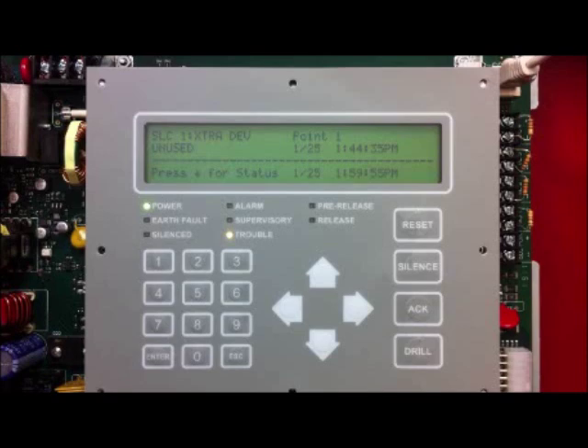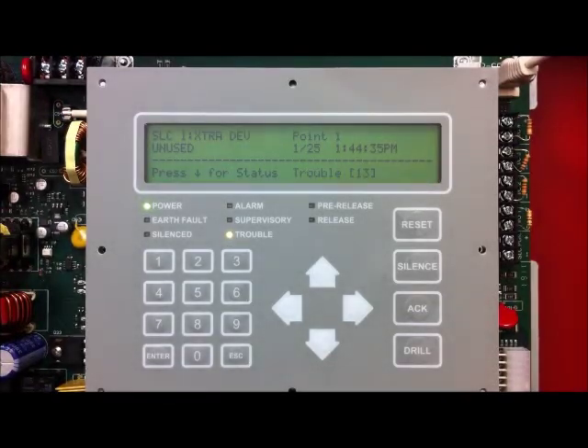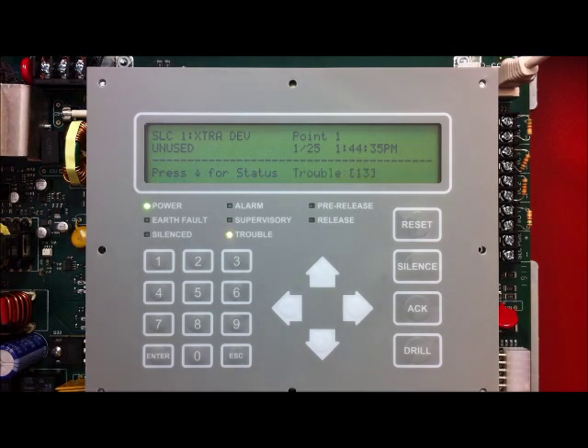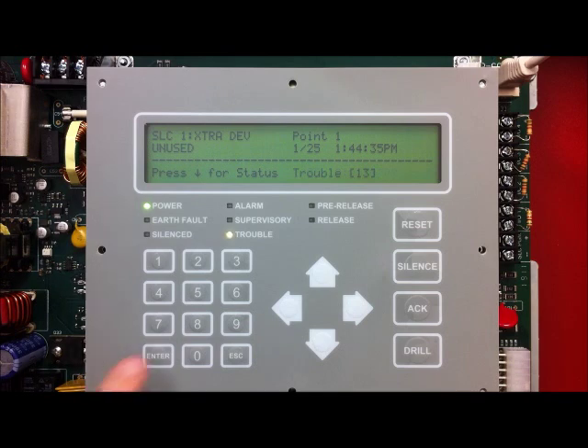In this video, I will be using a PFC 6800 to demonstrate the LEARN function. All the menu options you see me using today are the same for all of the PFC 6000 series panels. Once you have addressed all your devices, connect them to the SLC or the PLINK bus. Once you have made that connection, you will get several troubles from your SLC devices, indicated by an extra device. You should get the same number of troubles on your SLC as you have devices installed in the field. You are now ready to run a LEARN.